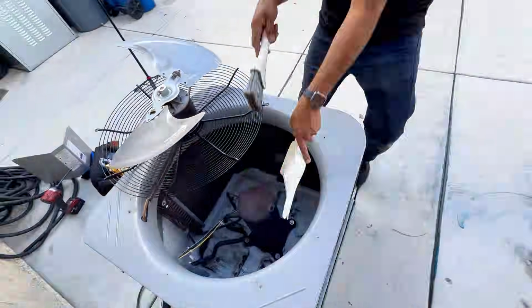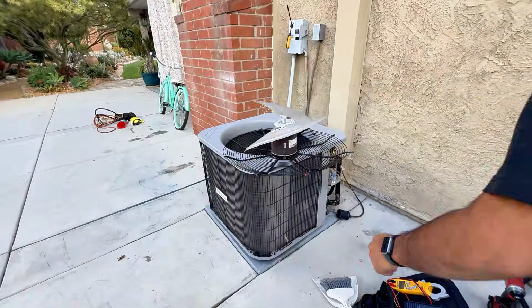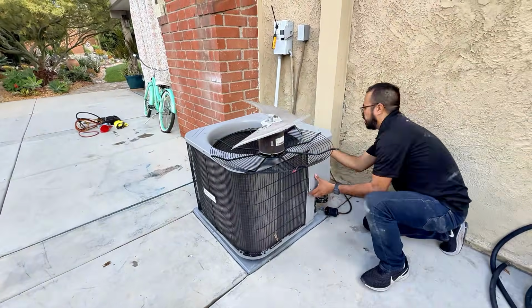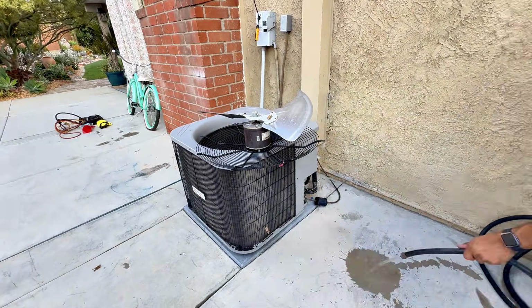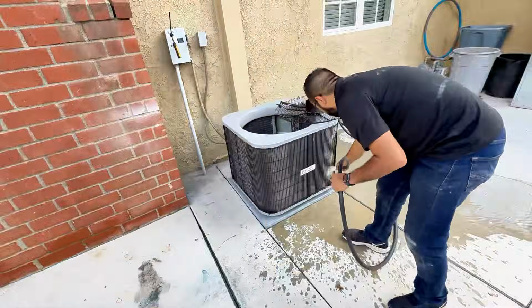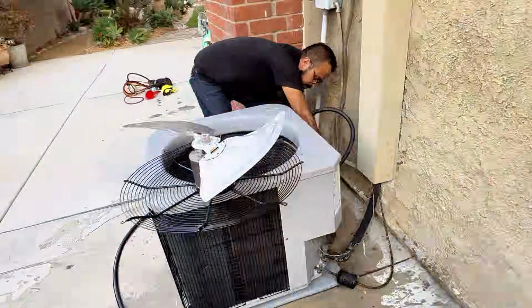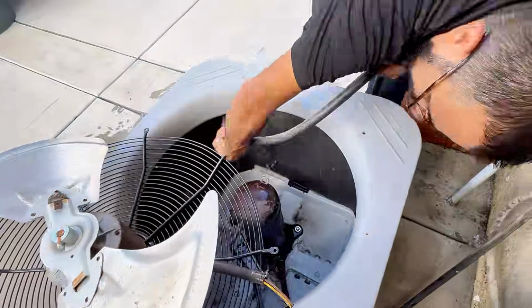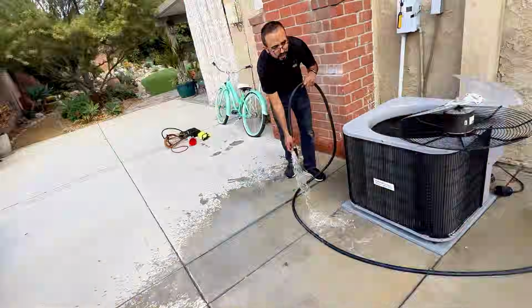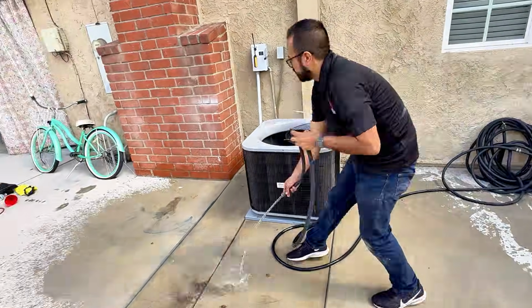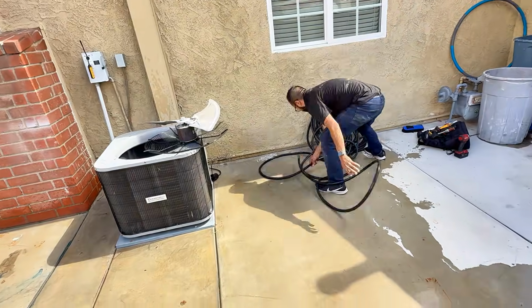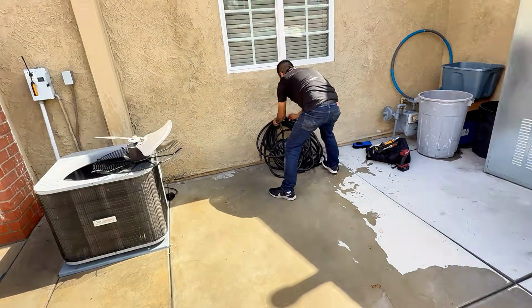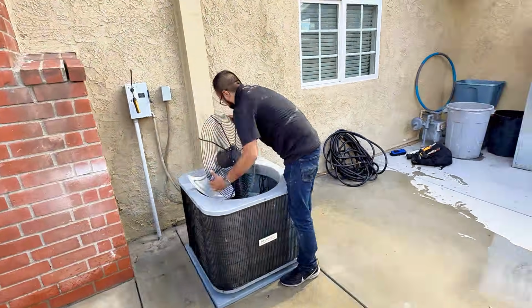So now I get my dustpan and clean all the debris and leaves that are inside. Then I put my tools away, or at least to the side, so they don't get wet. I put that panel back, keeping the electrical part dry, and I'm using the water hose to go from the outside in and from the inside out, washing out all that dirty water on the floor so it doesn't get sucked back in by the condenser fan.